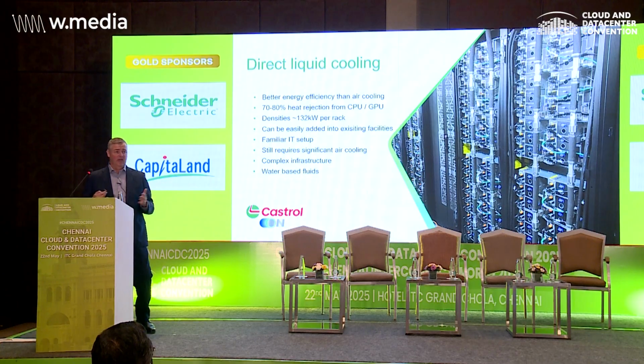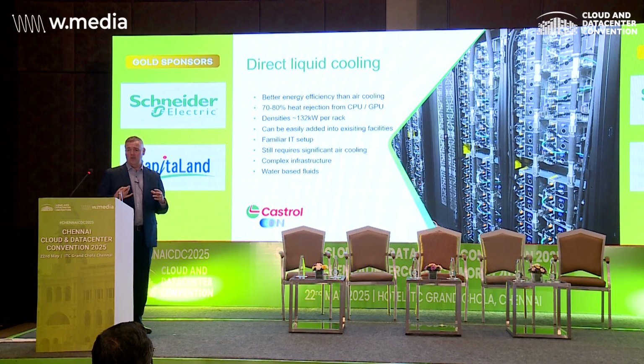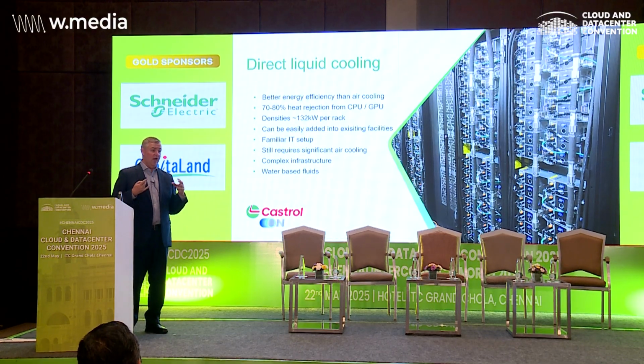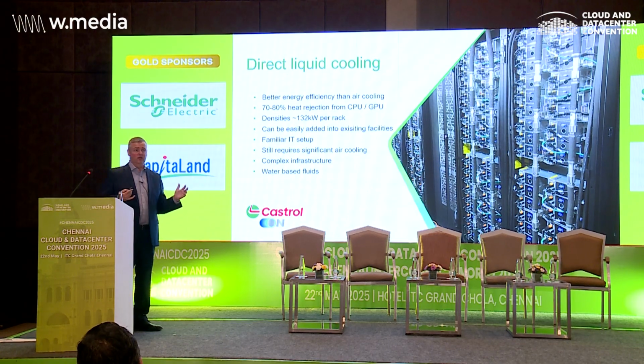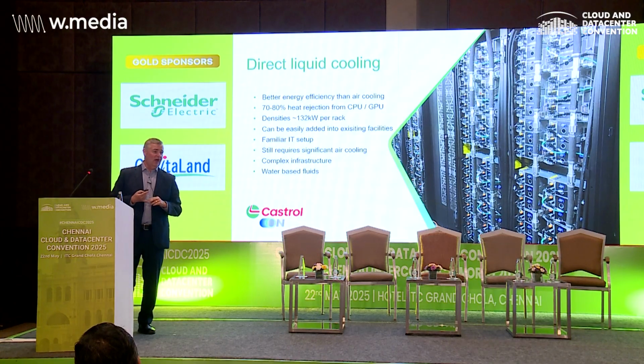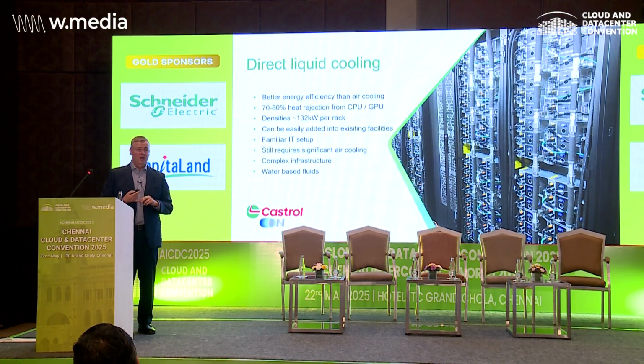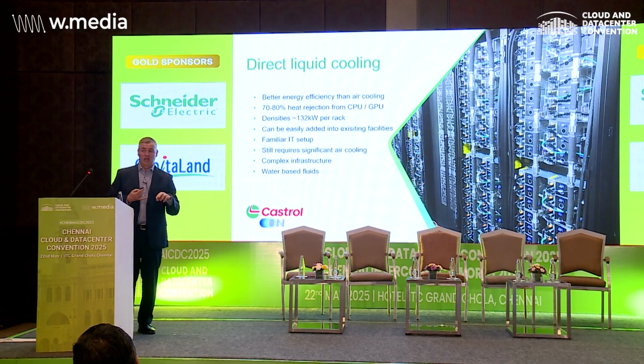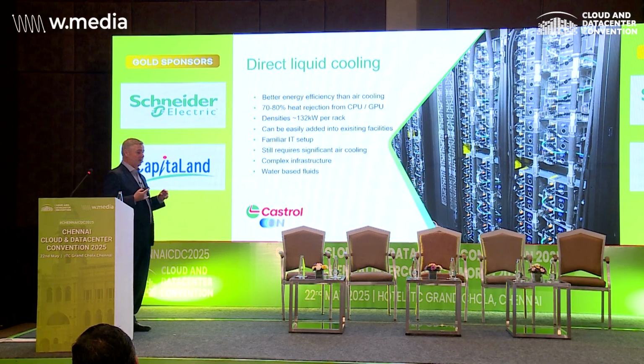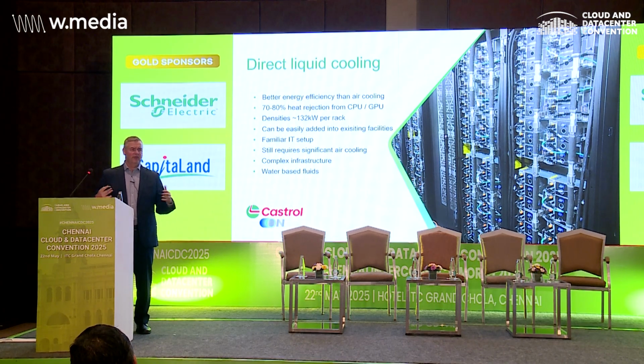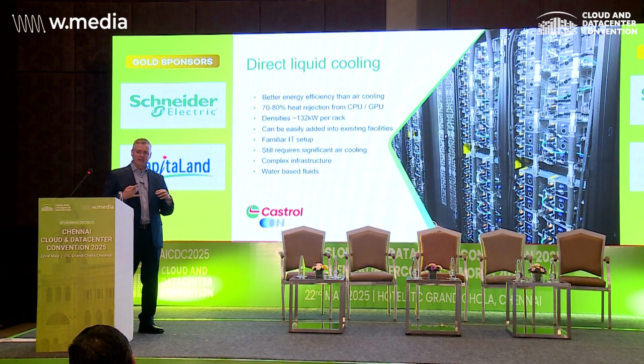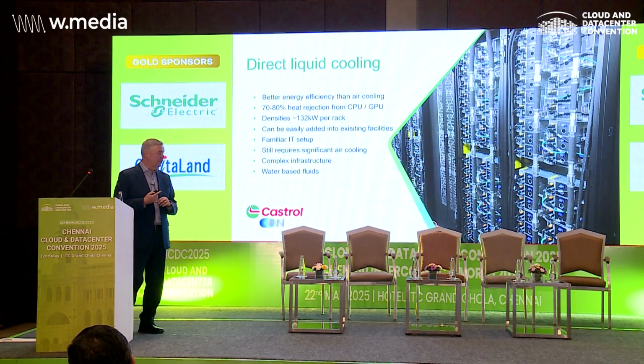DLC is far more efficient than air - it enables us to reject between 70 and 80% of the actual total server power or server heat. In terms of densities, there's so many NVL72s at 132 kilowatts being deployed around Asia Pacific and in India at the moment. One of the reasons for its adoption is that it's a more familiar technology - we operate with the IT in a very similar manner to what we already understand in the data center, so data centers are positioned to adopt this technology pretty easily today.